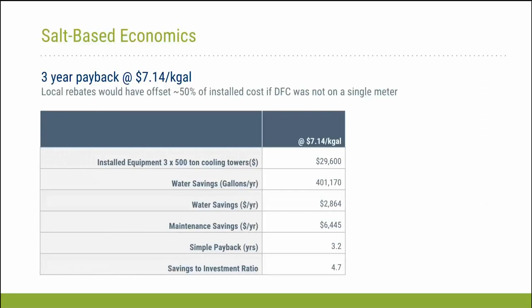So just quickly through the economics on this one, you're seeing a water savings of about $2,800 per year. Again, Denver does have cheaper water than the regional average for GSA. I think the regional average is right around $16 per 1,000 gallons. So, in these systems, things like water savings, chiller energy savings, and maintenance savings all do have a big impact. You can see, for example, the reduction in the chemical costs was about the same as the cost for the water savings. But the total maintenance savings was $6,445 per year, and the simple payback on this one was 3.2 years. Okay, next slide.